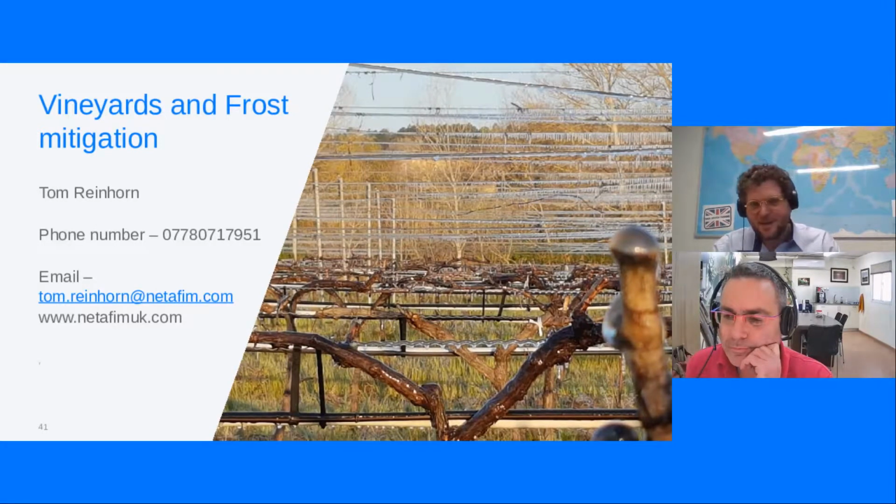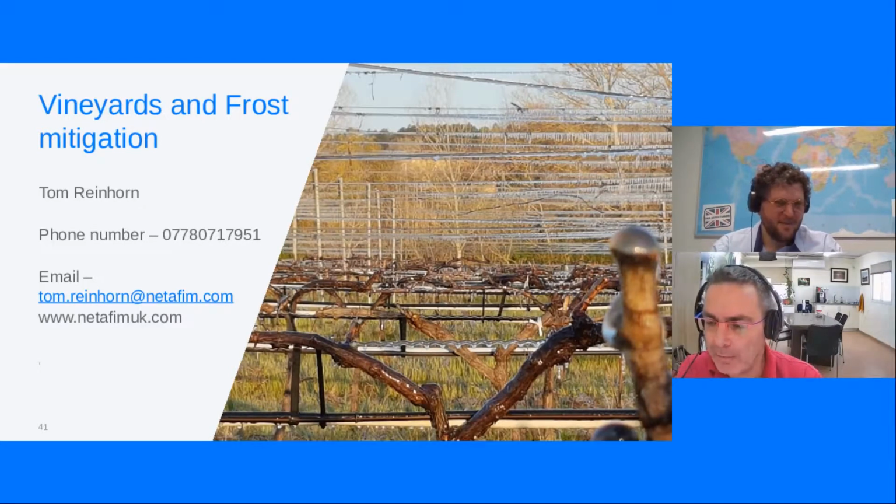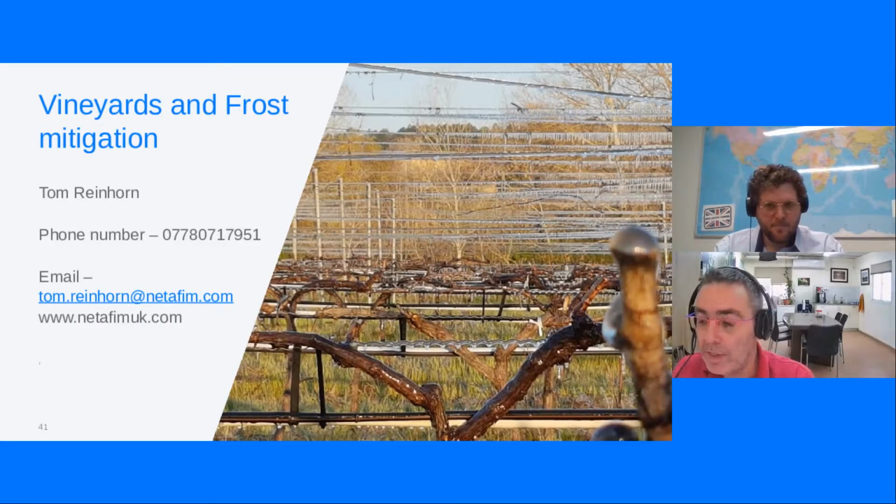I think yeah, you can. It's subject to proper hydraulic design. The infrastructure, which means pump, valves, head system, mains, submains, can be used, and in many cases under vineyard conditions and plant scheme, we've been able to use the same infrastructure for irrigation with drip and frost fighting with pulsar. This is one of the advantages of using a low flow frost fighting system. You can use the same infrastructure, but don't do it on your own. Consult a hydraulic designer in order to make it for you.